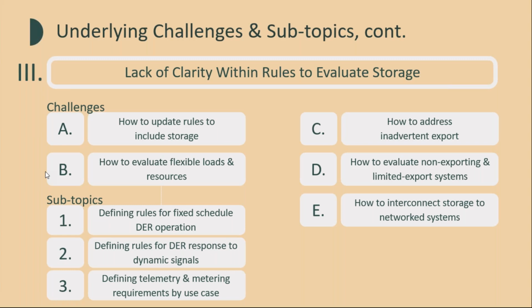So it kind of allows for a type of reconfiguration on the fly, and it uses specialized equipment called network protectors in order to make that happen and ensure that power is not flowing in the wrong direction. This also makes interconnecting a generator or DER to a network system much more challenging, because you cannot feed back much power onto the distribution network - you could potentially risk flowing power in the wrong direction through a network protector and tripping it offline even when there is not a fault. So systems like that have to be reviewed rather carefully, or potentially limited in power output.